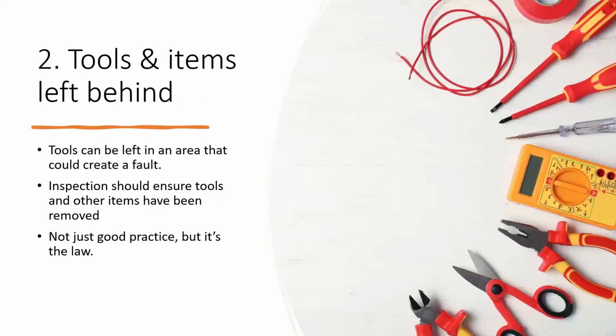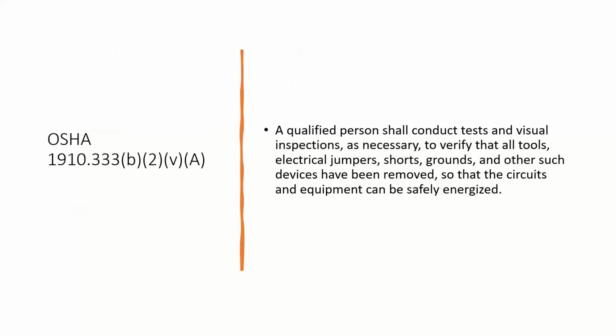The second bullet point was tools and items left behind. Tools can be left behind in an area that could create a fault. Inspection should always happen to ensure tools and other items have been removed. And it's not just good practice, it is also the law according to OSHA. Let's take a look at that. It says a qualified person shall conduct tests and visual inspections as necessary to verify that all tools, electrical jumpers, shorts, grounds, and other such devices have been removed so that the circuits and equipment can be safely energized.